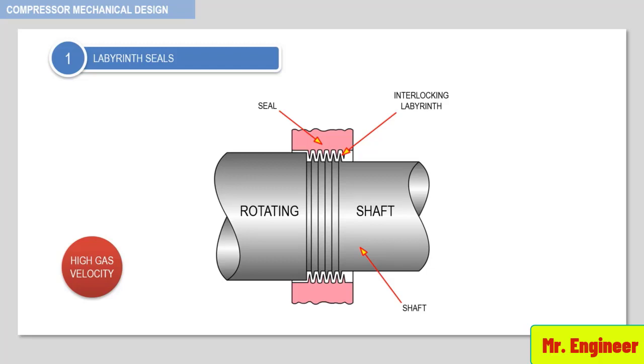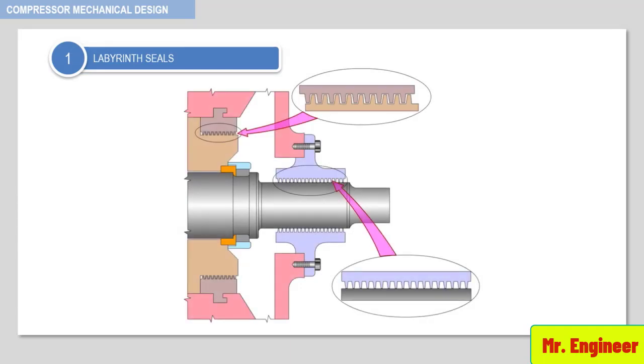In many process applications, you will find arrangements employing both simple and interlocking labyrinth seals. Here you can see the simple labyrinth seal and the interlocking labyrinth seal. Keep in mind, though, that labyrinth seals do not completely prevent leakage. They are widely used as interstage seals, where the pressure differential required across the stage is small enough for the labyrinth seal to be effective.